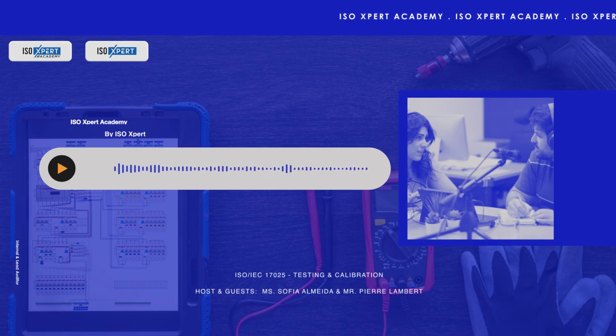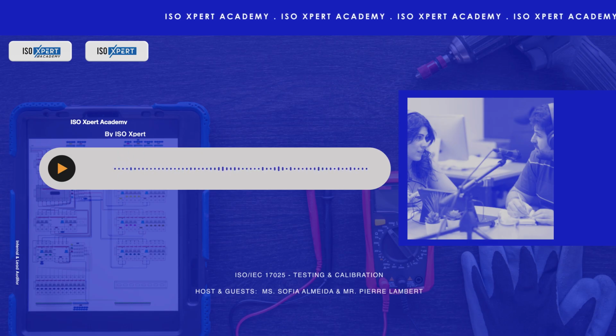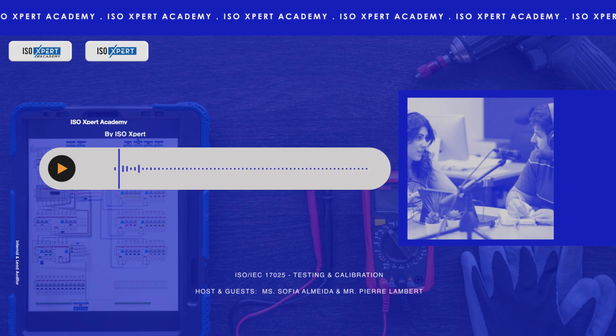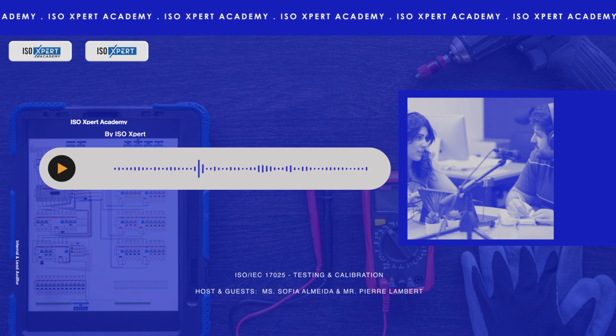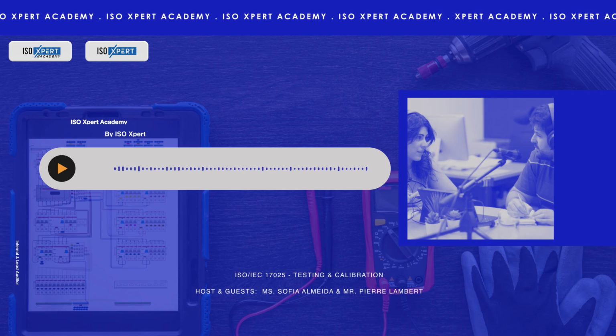They look for calibration labels on the equipment itself. And they review maintenance records. Is preventative maintenance being done? Is broken equipment taken out of service correctly? It's about ensuring every instrument is trustworthy. And this calibration aspect leads directly into something really fundamental in science, doesn't it? Metrological traceability. Yes. 6.5 metrological traceability.